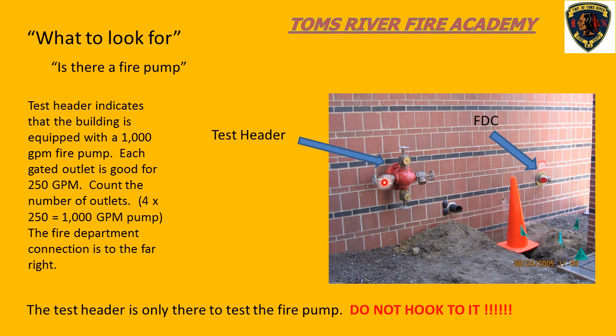Every one of these valves is good for 250 GPM. So in this case, we have 4 250 GPM valves, so that tells us that there's a 1000 GPM fire pump in the building. But again, it may only be rated at 40 or 50 psi, whatever the pressure is needed to meet the hydraulic demand of the sprinkler system. So again, if you see something like this, go ahead, hook up to the fire department connection, get the needed pressure into the system, and then go in and shut the fire pump off.